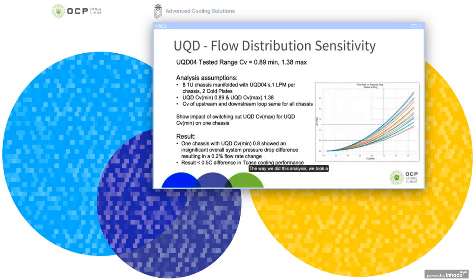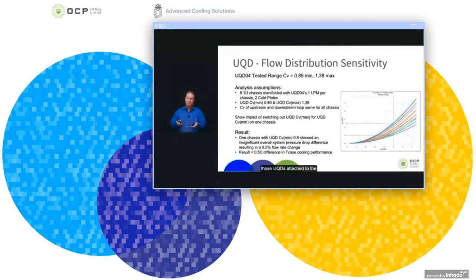The way we did this analysis, we took a representative system that we're working on currently, and if you can imagine the UQDs in a system, maybe all of those UQDs attached to the system are of the higher value CV, and then you take a system and switch one out with the lower value CV. Now you might think that that particular system might get starved for flow because of the CV values, and all of these systems were analyzed based on cold plate type design cooling loops.